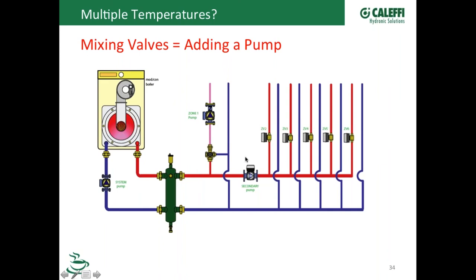No, it won't. And the other thing to be aware of here, too, is watch the CV on these valves. You know, that little mixing valve, if it had a 3 CV valve and you have a demand out here for 10, 15 gallons per minute, you don't have enough valve to be able to supply that kind of flow going through. So make sure when you're sizing these two devices that you've got enough capacity in the valve to do the flow rate that you need.